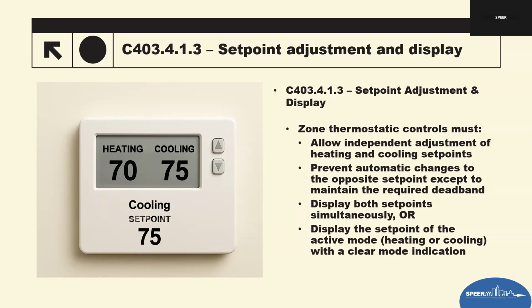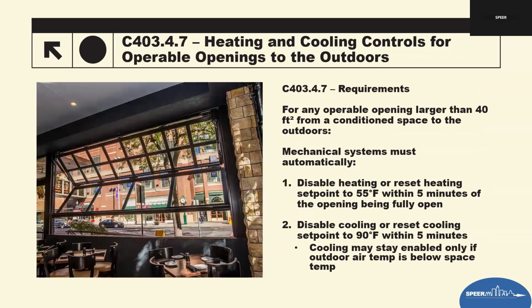Can the user adjust heating and cooling independently? If so, it meets the compliance. If not, it does not. Are both set points visible, or is it showing an active mode only, showing you the set point? So if you switch it to heating, you'll see that set point. Cooling, you'll see that set point. Whatever's running, that set point is being shown. And then does the thermostat prevent a deadband less than 1 degree? And then does adjusting one set point avoid unwanted automatic adjustments? So that's field verification with that.